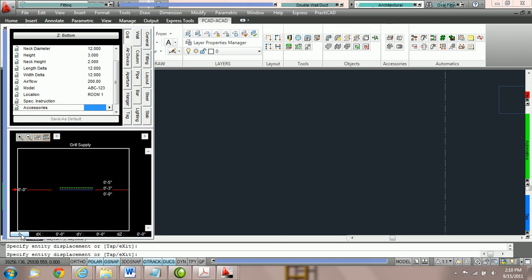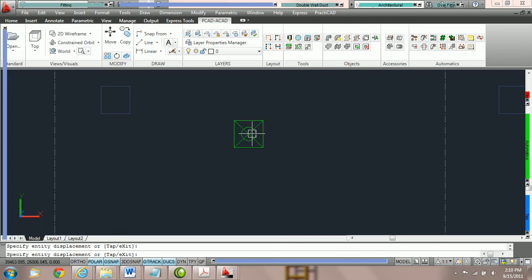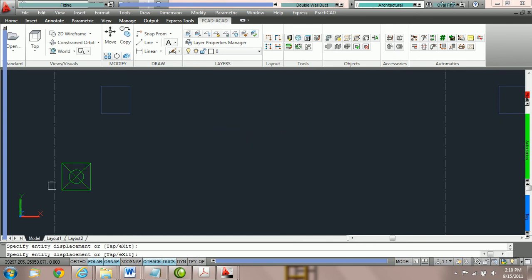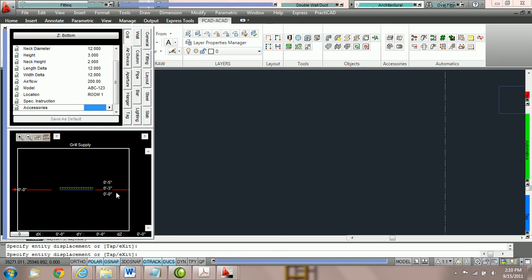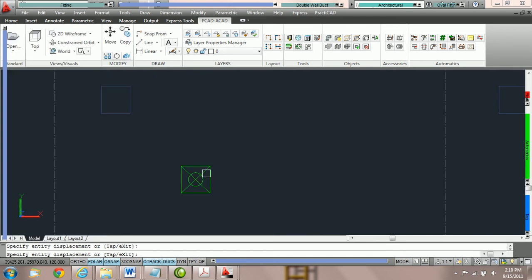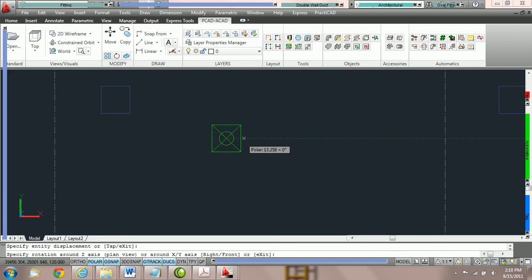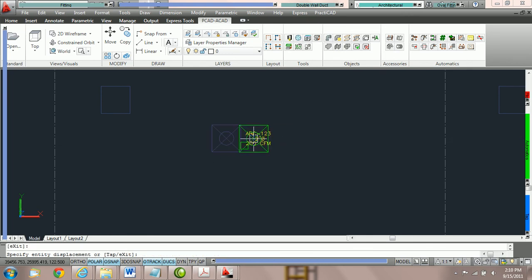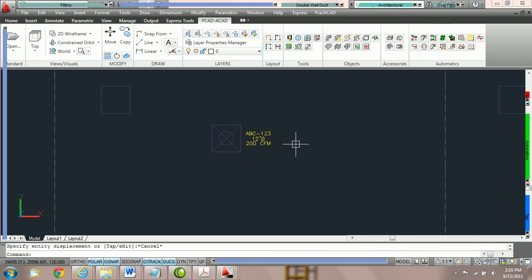I'm going to reset this actual elevation DX, DY, DZ feature to zero. And what we're now going to do is we're just going to place this down on the drawing at the height we want to place it. So what we're going to do is say let's put the bottom of this grill at 10 foot bottom and hit enter. Then place it on your drawing. I click once. It's asking for a rotation. I click again, and now it's placed.